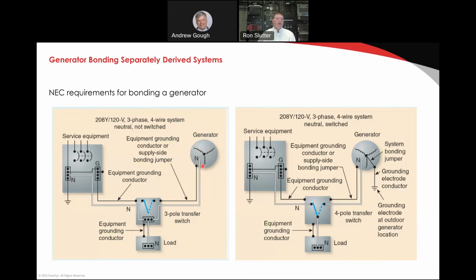You get circulating ground current. It's unsafe. It causes an equipment and a safety problem when we run into these situations. So there should only be one neutral to ground bond in this service equipment related to bonding a generator.